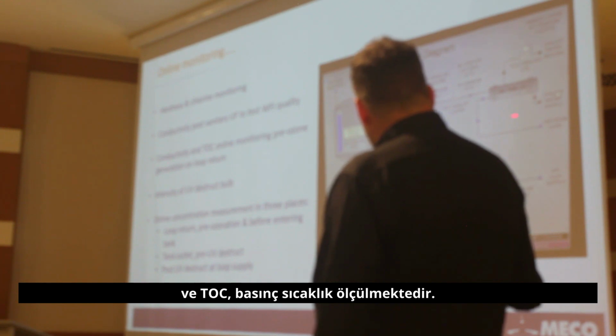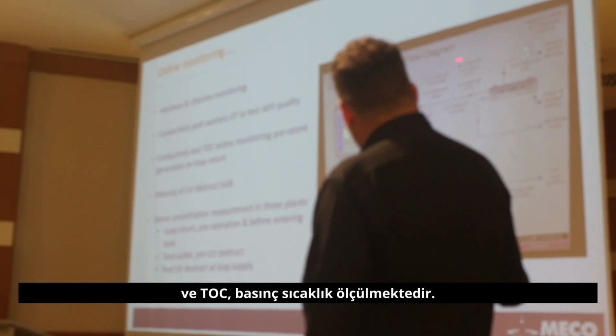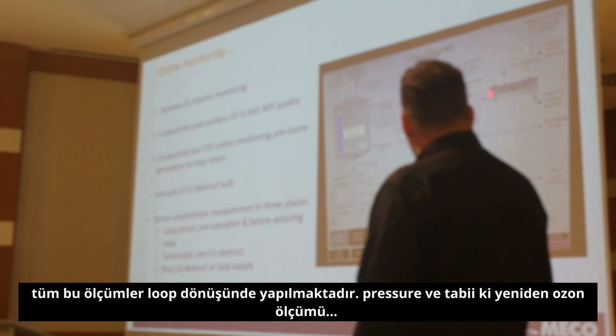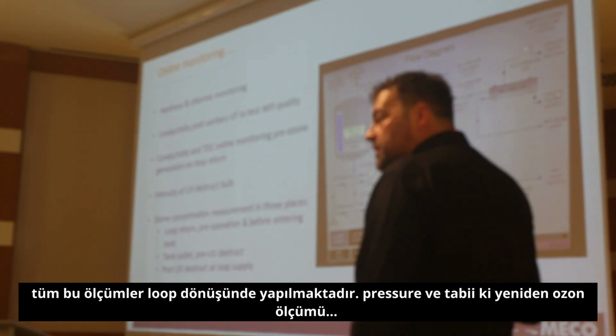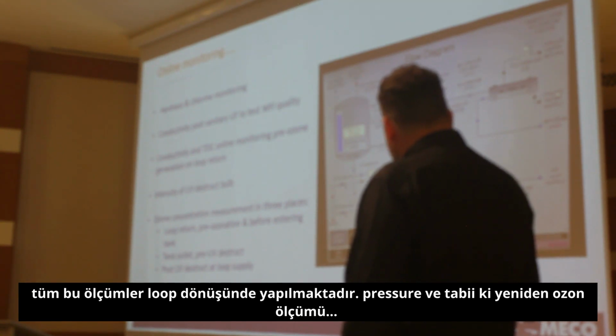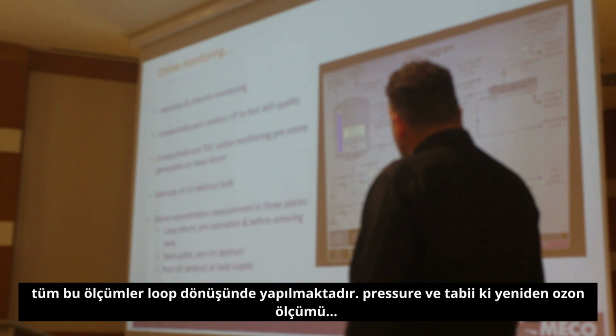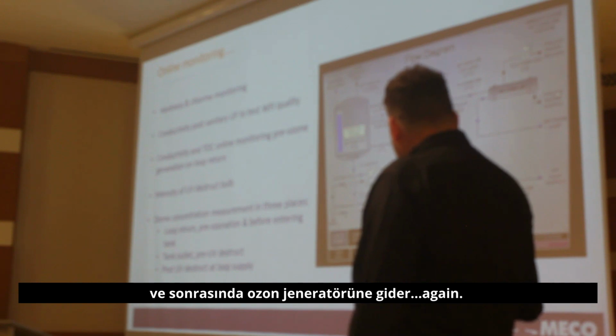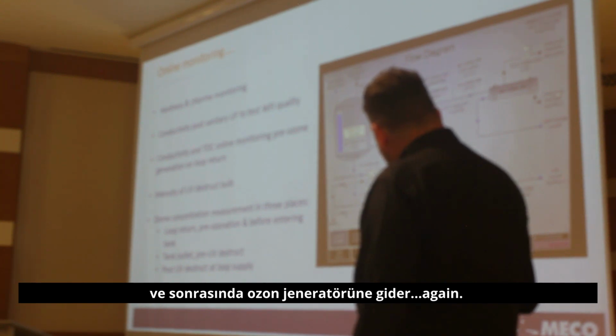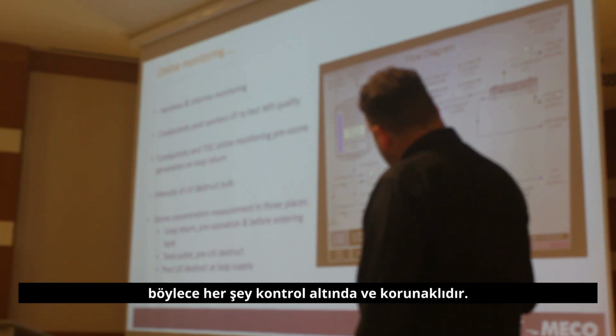We then measure our conductivity, TOC, temperature, pressure, and flow. Everything is measured at the loop return, plus the ozone again. Then comes the ozone generator, which injects fresh ozone generated from the water for injection, constantly into the loop return. So this is always protected.